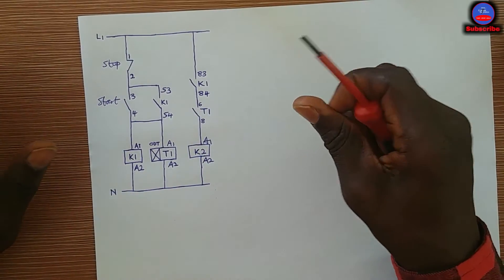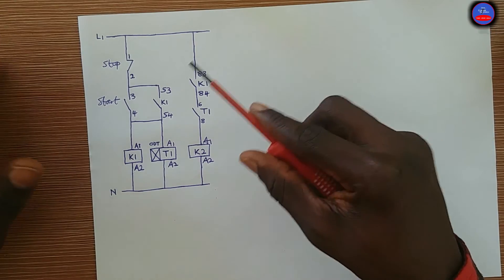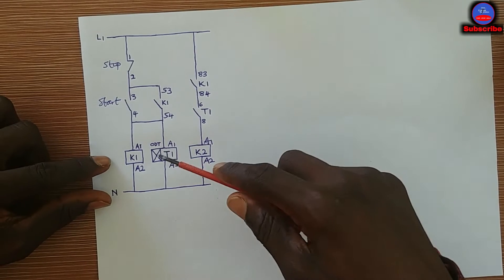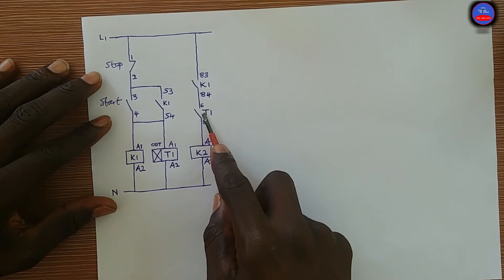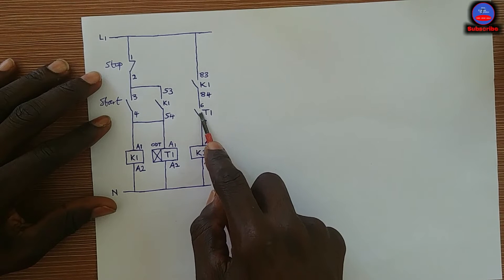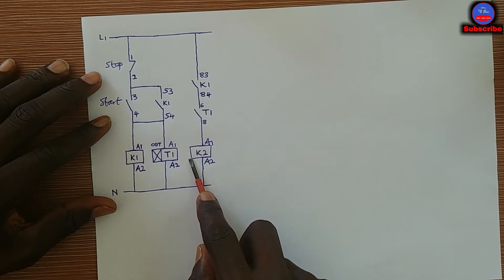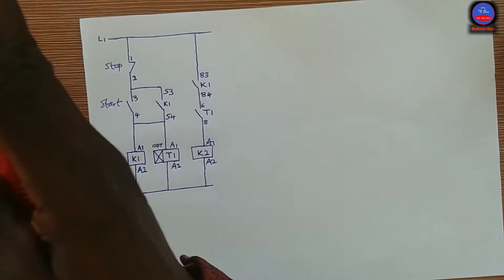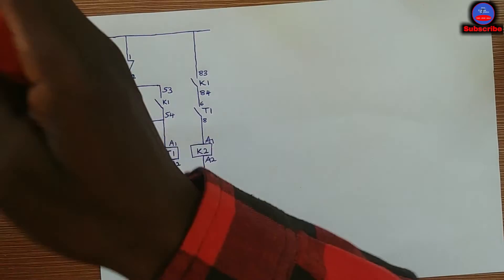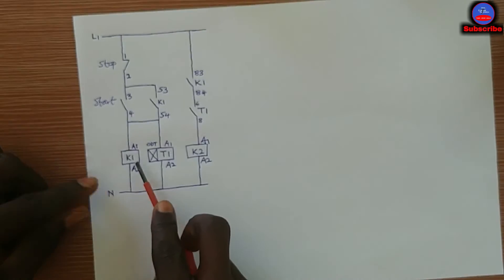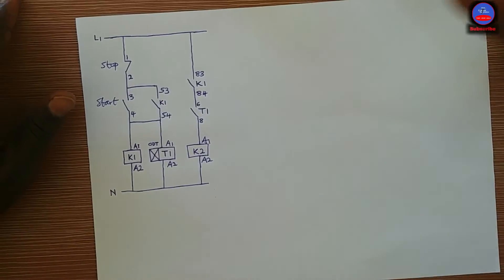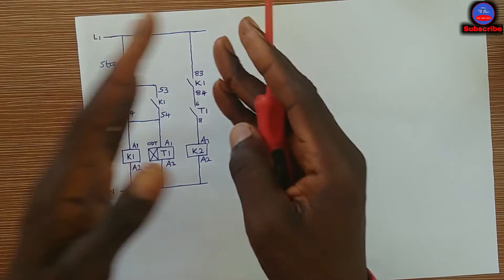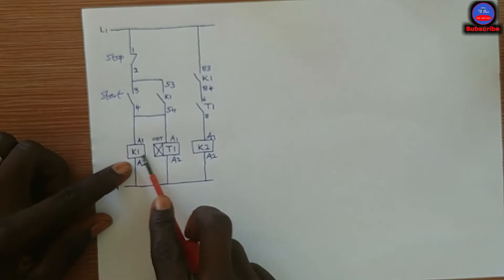When the timer energizes it also starts counting. Let's say we set the timer at six seconds or ten seconds — whatever preset time you give it. After that preset time, this normally open contact on the timer will close, and when it closes it energizes K2, the Contactor 2 or Motor 2. So in this circuit the motors always operate in sequence: Contactor 1 must be in operation for some time before Contactor 2 energizes.